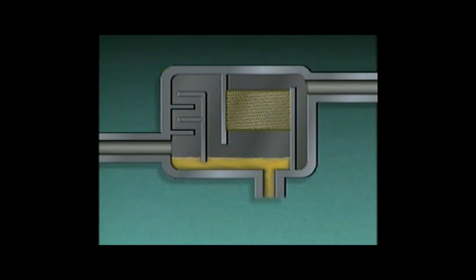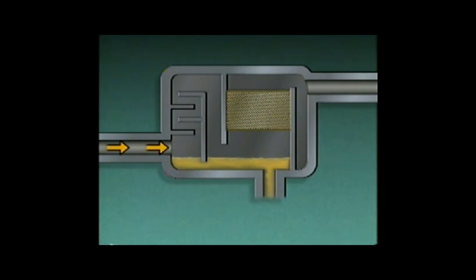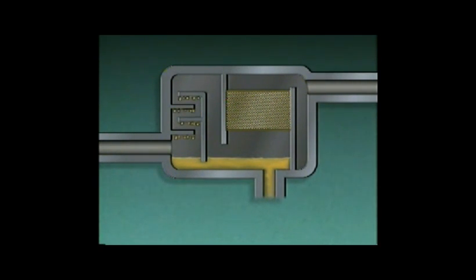An oil separator includes an inlet, a series of baffle plates, a wire mesh screen, a sump, and a gas outlet. Compressed gas entering the oil separator passes around the baffle plates and is forced to make rapid changes in direction. Because oil is heavier than gas, it is more difficult for the oil to make these changes in direction. As a result, oil droplets separate from the gas, collect on the baffles, and drip down into the sump. In this way, most of the oil is removed from the gas.